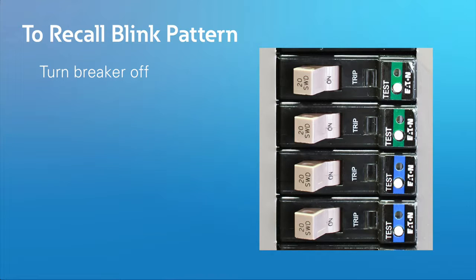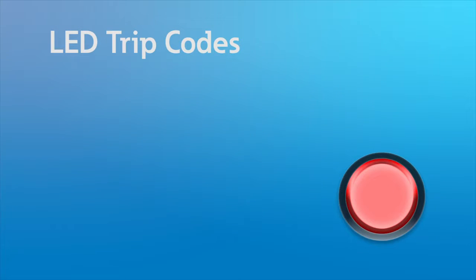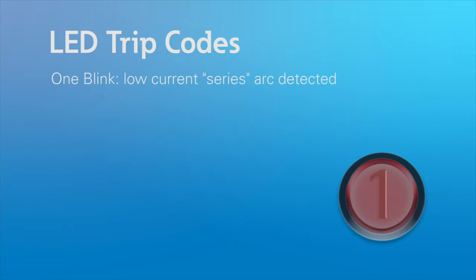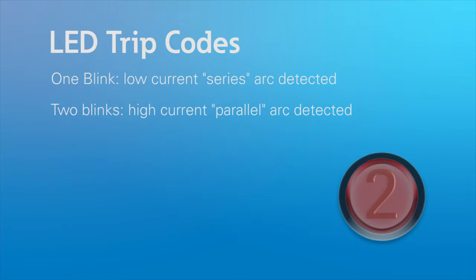The trip codes that the AFCI breakers communicate include the following: 1 blink. A low current series arc has been detected within one of the circuits. These arcs are typically found in worn or degraded appliance and extension cords, poor connections in appliances or fixtures, or in contacts within equipment. 2 blinks. A high current parallel arc has been detected between two conductors. These arcs are usually found in installed wiring where the wire has been compromised by a nail or screw, tight staple, or damaged insulation.